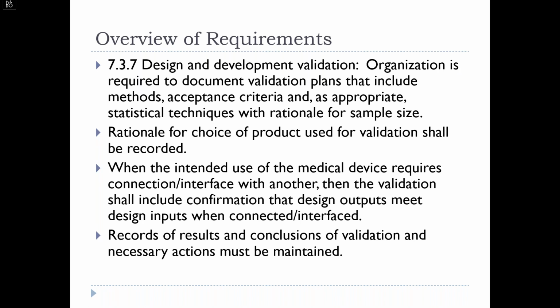You're going to see some parallels here with design validation. First, the organization is required to document the validation plans, including methods and acceptance criteria, and statistical techniques with regard to sampling size if sampling is to be employed. Rationale for choice of product used for validation needs to be recorded. Again, when the intended use of the medical device requires interface with another, the validation needs to take place when that is connected or interfaced. And records of the results of any design validation activities and necessary actions must be maintained.